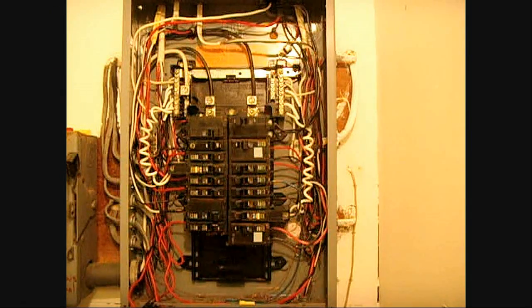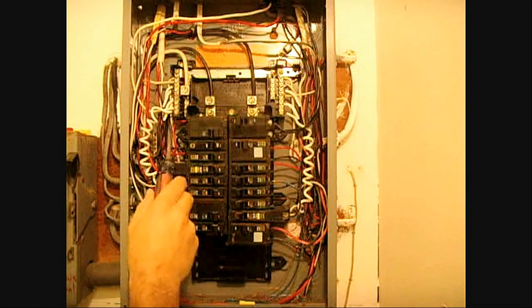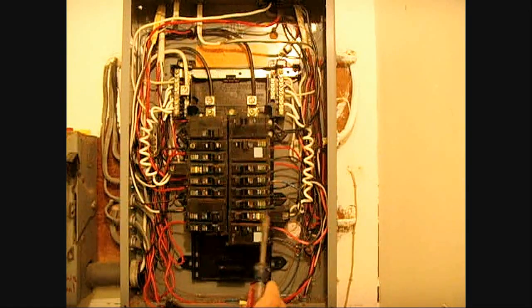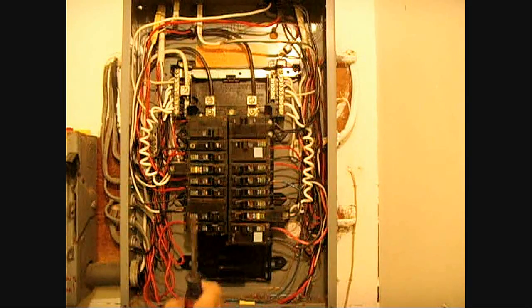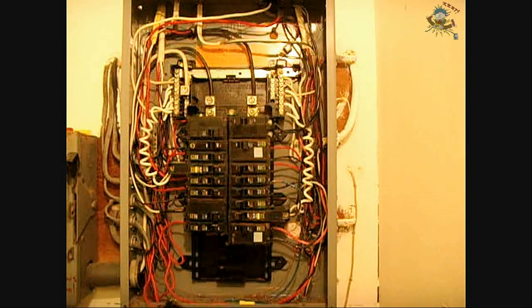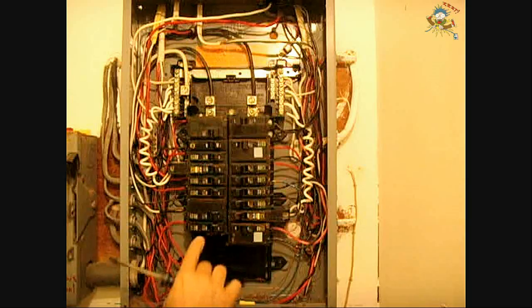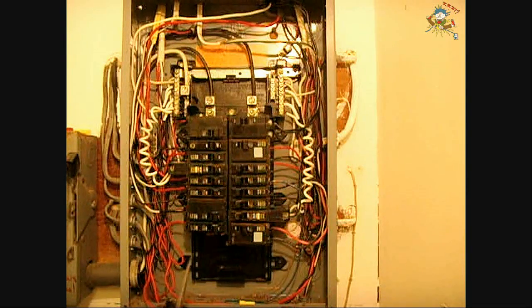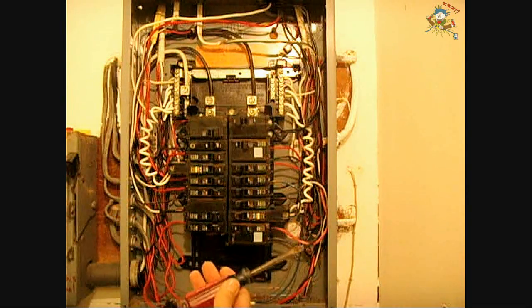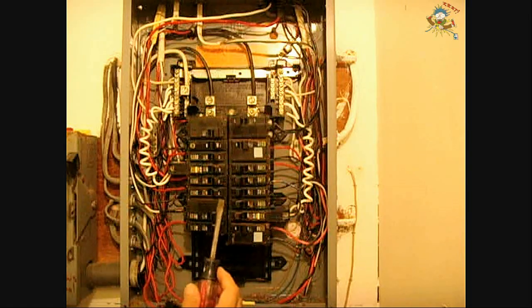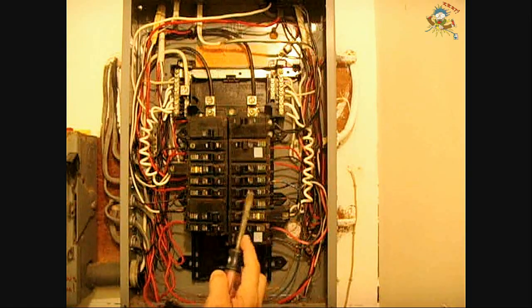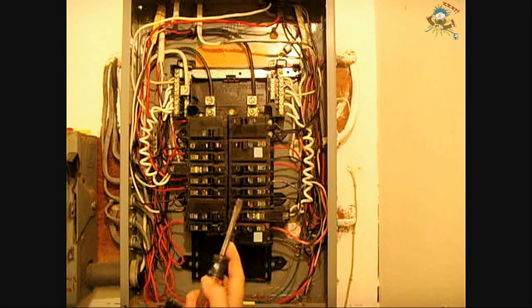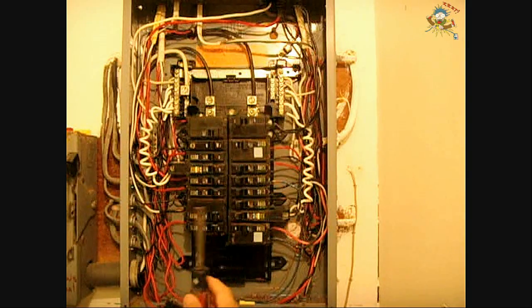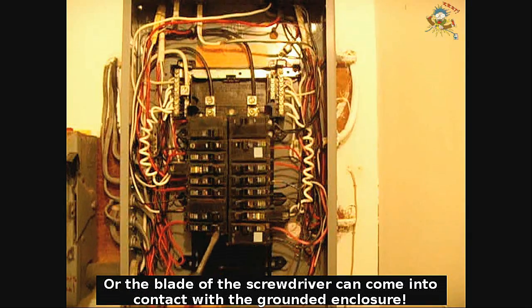I'm going to leave this one out because I'm going to want to show you the bus bars in a minute. You're going to want to check every single one of these screws on all these breakers. Make sure it's very secure. Turn off each breaker as you check each screw. When you're done checking each screw, turn it back on. You don't want to do it while it's on, even though I do it that way, because there's always a chance you might forget and your finger might come in contact with the blade of the screwdriver and you can get a very painful or even a lethal shock. So make sure you turn the breaker off.